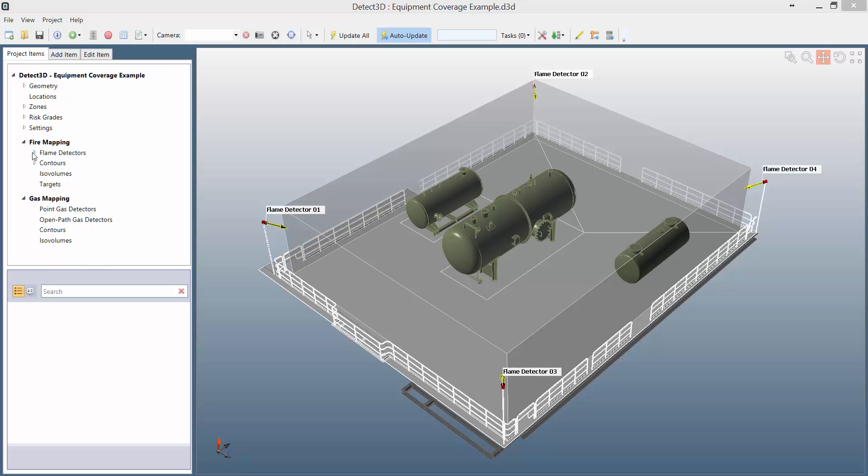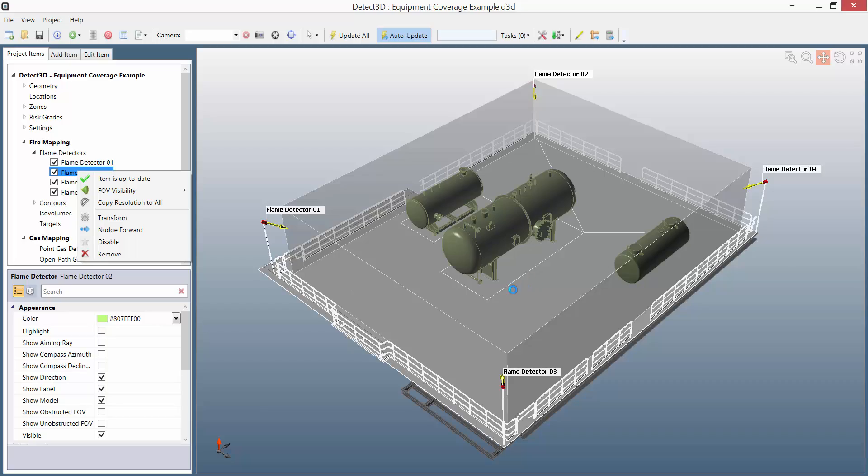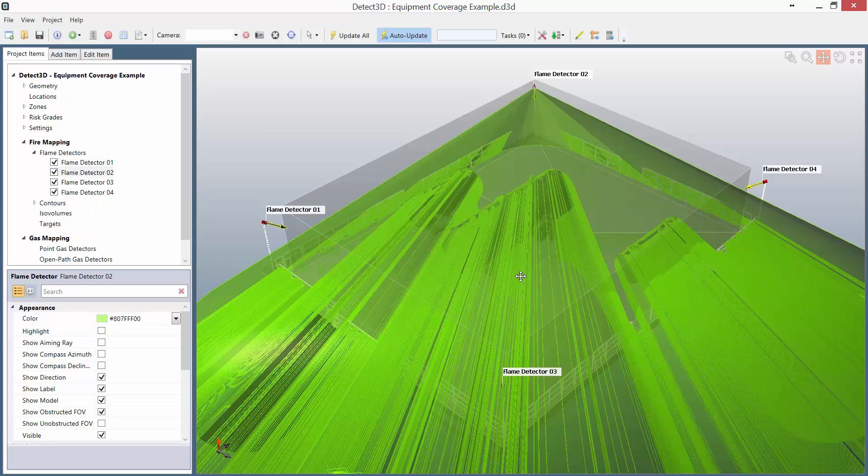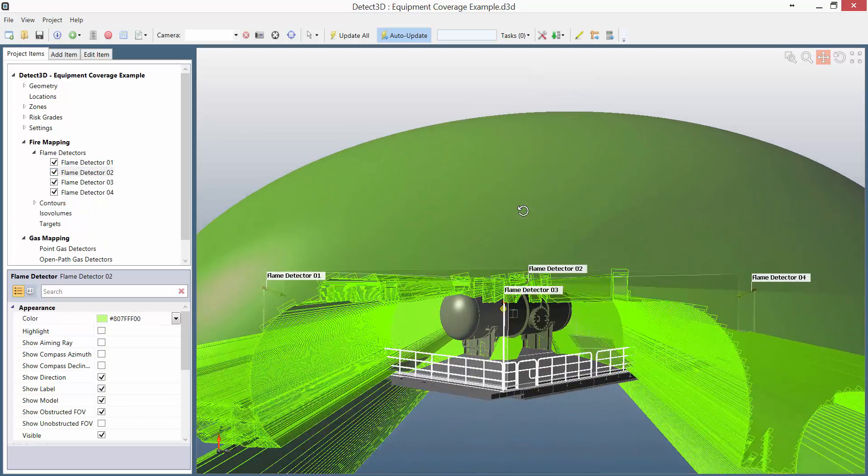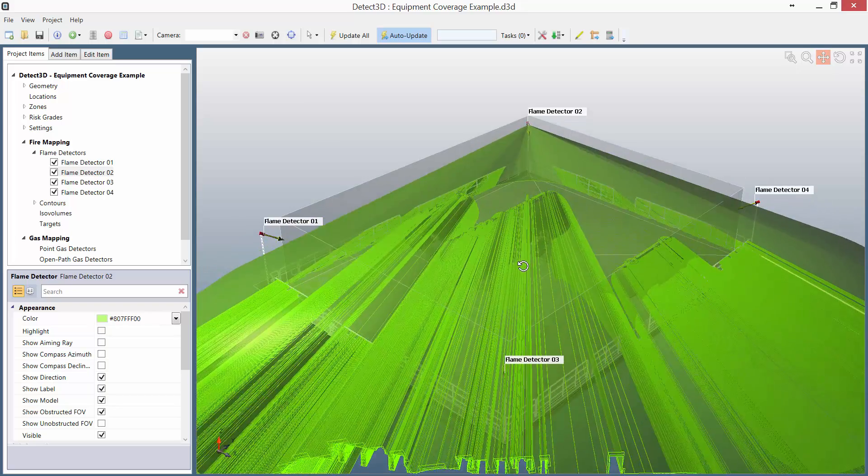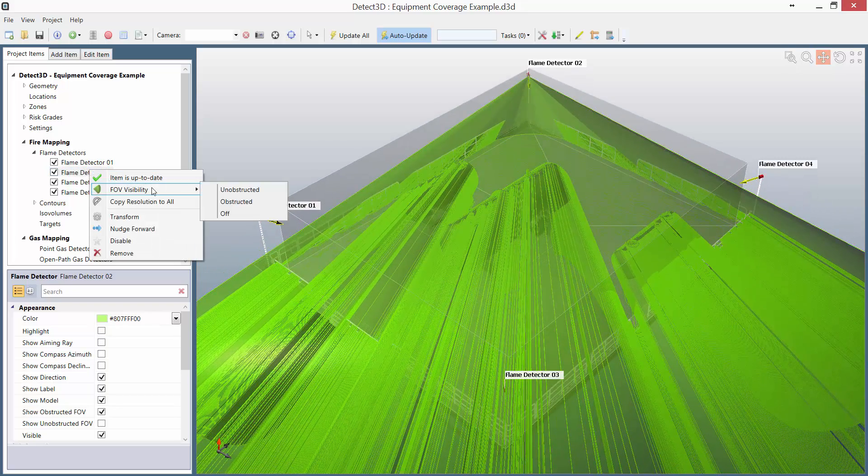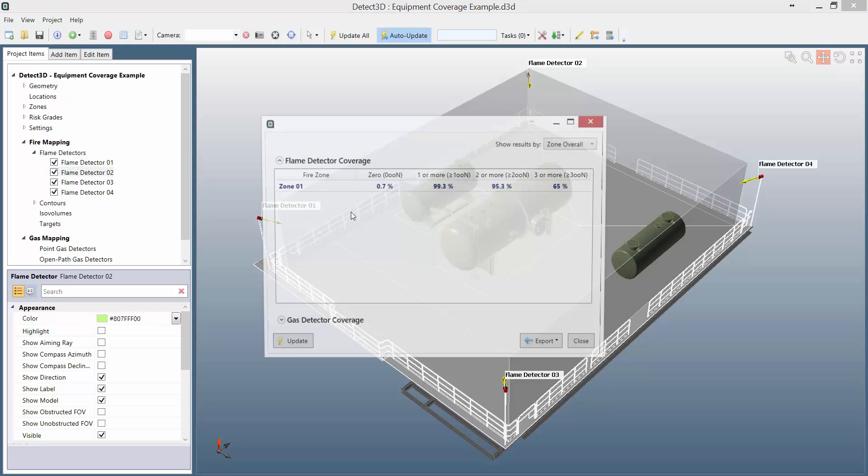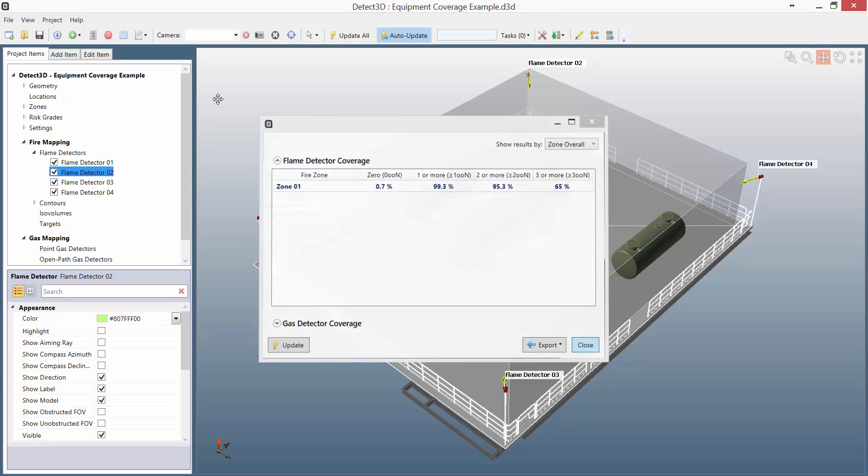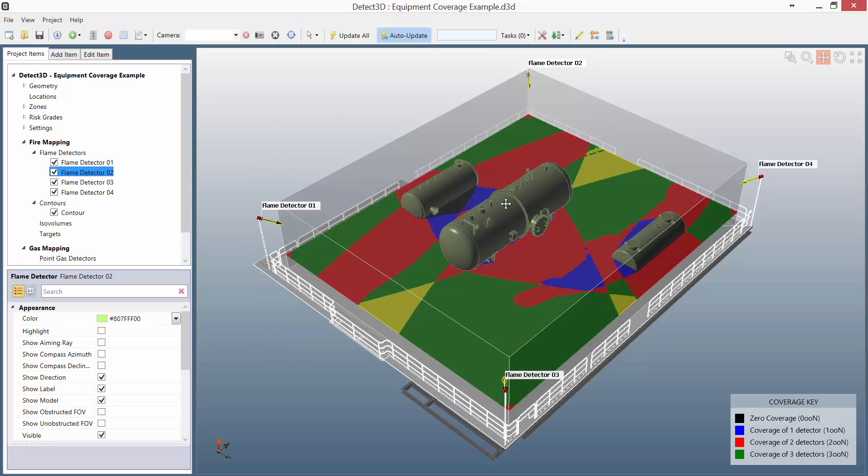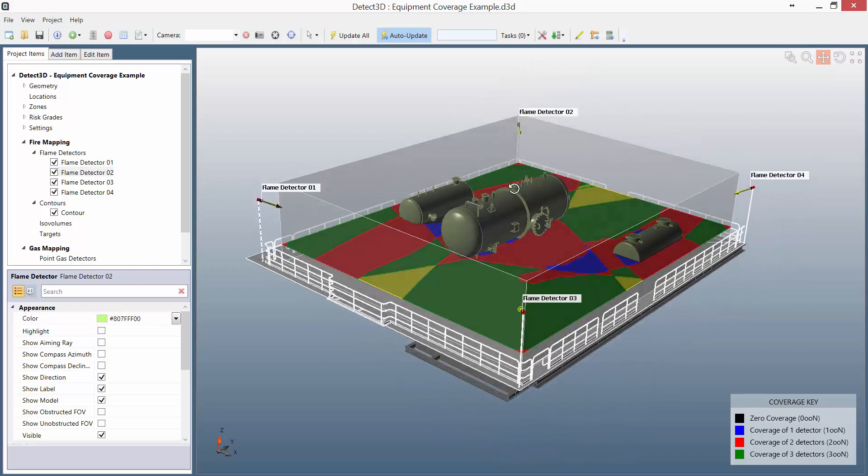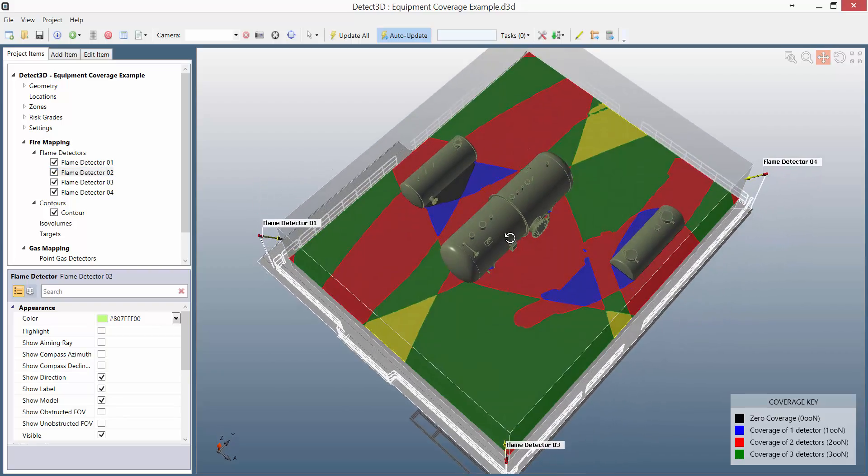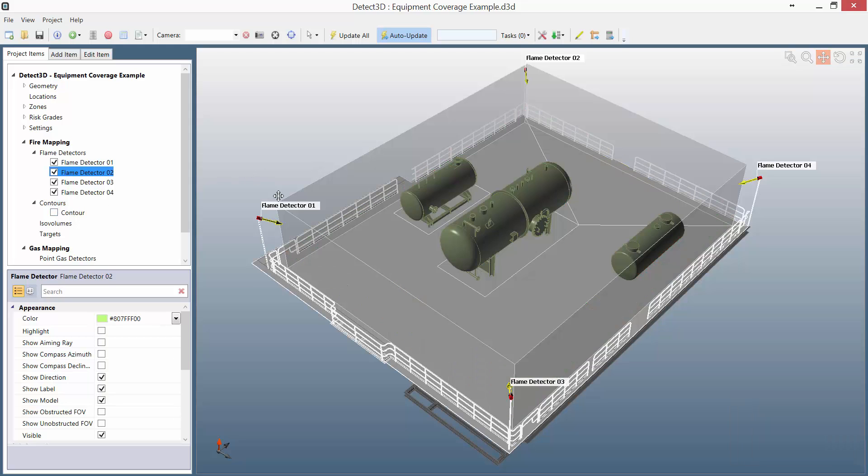In this example, I've set up the flame detector's field of view for a 10kW fire. You can see the obstructed field view for one of the detectors here. For smaller fires, the field of view is smaller, and for larger fires, it's bigger. You can of course see the coverage, and this coverage is valid for the 10kW fire that I set up my flame detectors for. The same is true with the contours. If you look at this contour here, it's really only valid for the detection of a 10kW fire, as that's what I have my flame detectors set to.